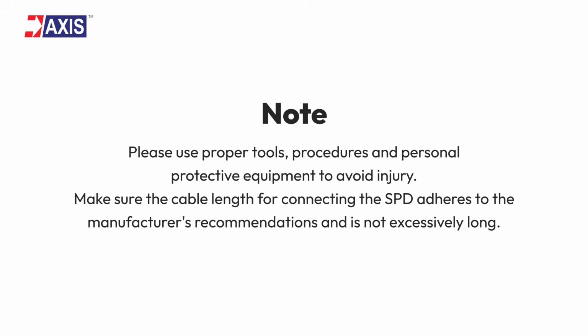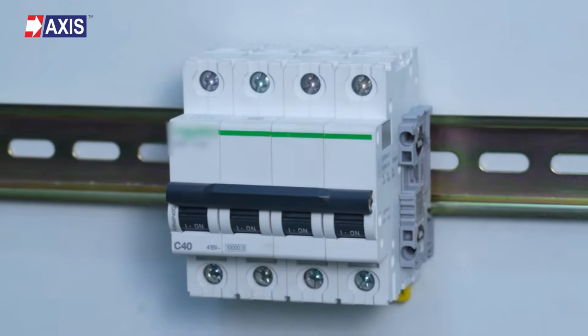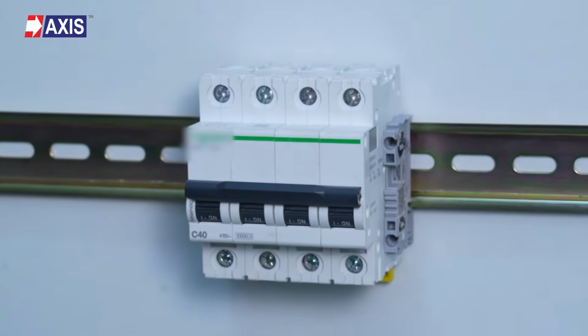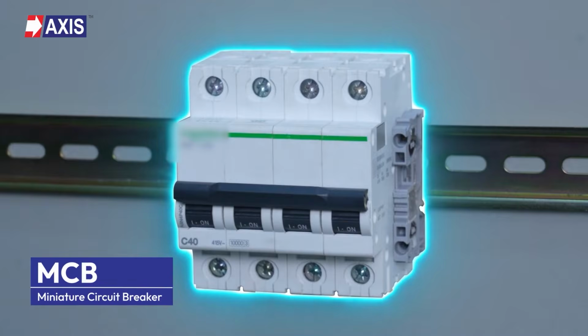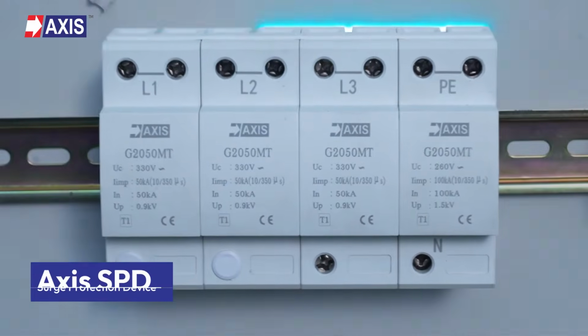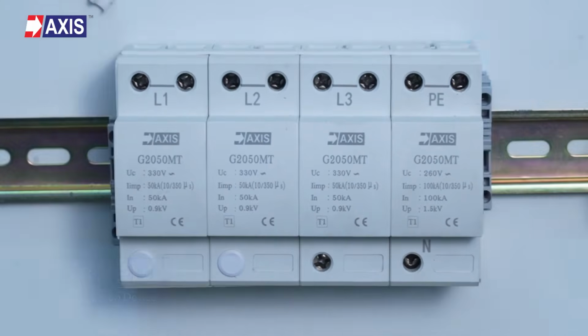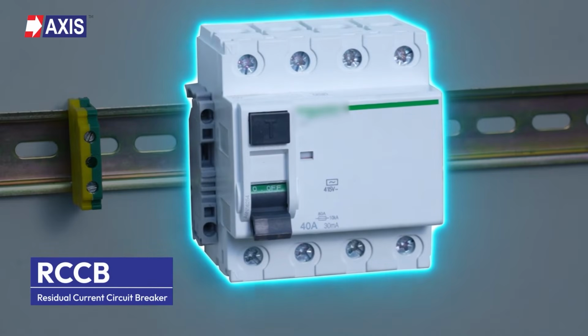Make sure the cable length for connecting the SPD adheres to the manufacturer's recommendations and is not excessively long. Now, look at the devices here. The first is an MCB. The second is the Axis SPD, and the third is an RCCB.